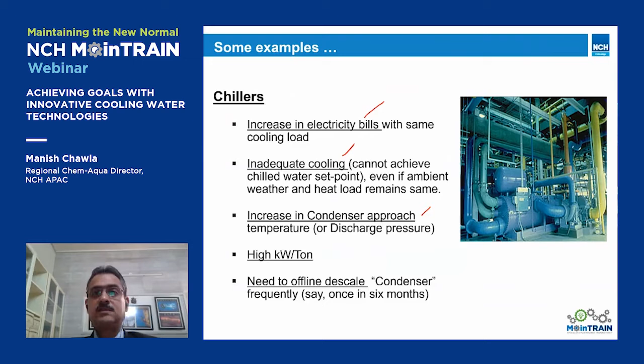One example is water cooled chillers. If you find your electricity bill rising even though the cooling load remains the same, you have a problem. Or you're not able to achieve your chill water set point, or your condenser approach increases very fast—maybe from 1 degree Celsius to three in a year. Your kilowatt per ton, if you're monitoring that, or if you have to open and clean the condenser very frequently, and when you open it you don't find pure copper color but some deposit or scale.